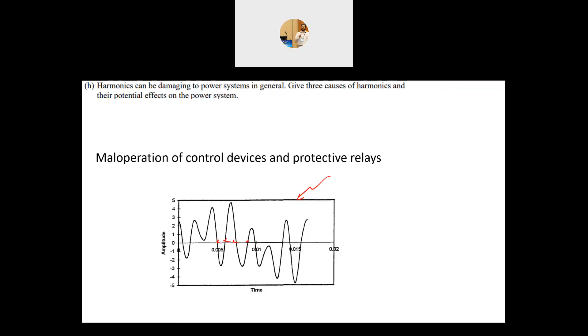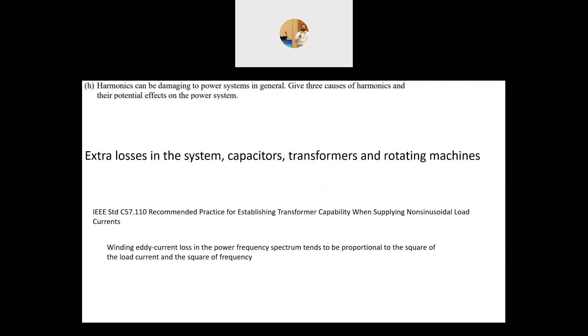Another severe issue with harmonics is it causes extra losses in capacitors, transformers, and rotating machines. The current is not only the fundamental but has harmonics. As per IEEE standard C57.110, the winding eddy current loss in transformers at power frequency rating is proportional to the square of the current—I squared R—but also proportional to the square of the frequency.